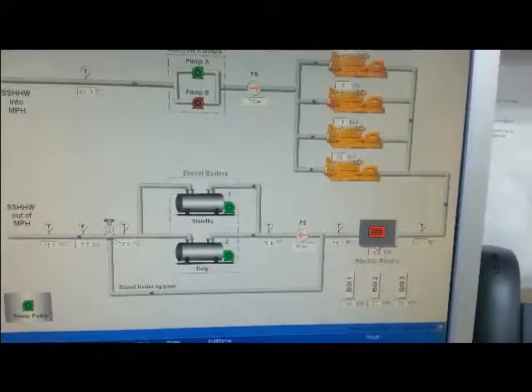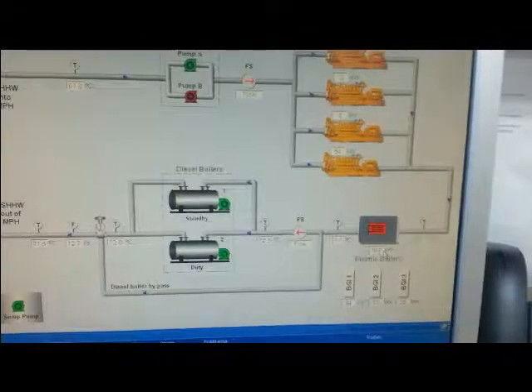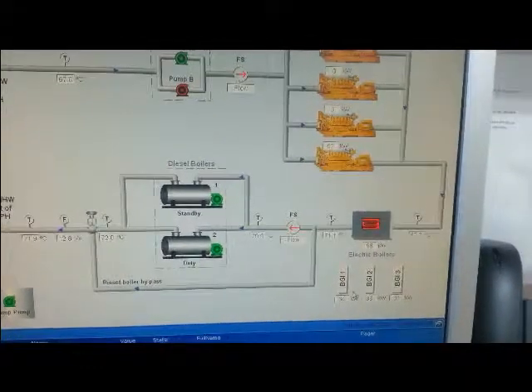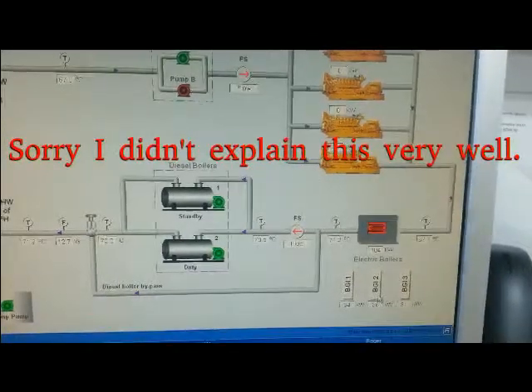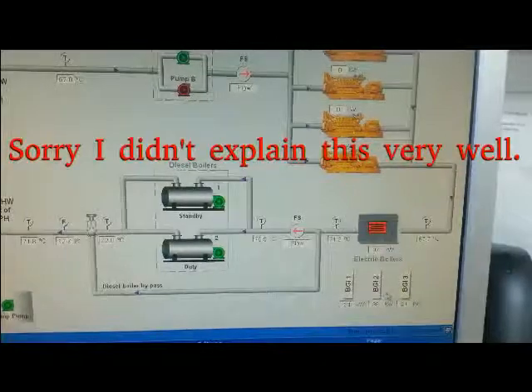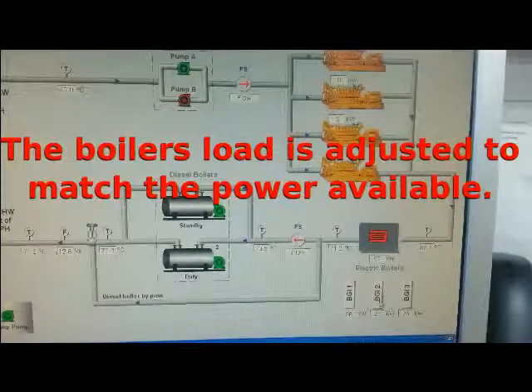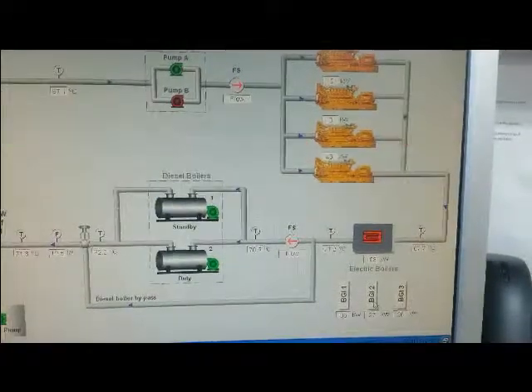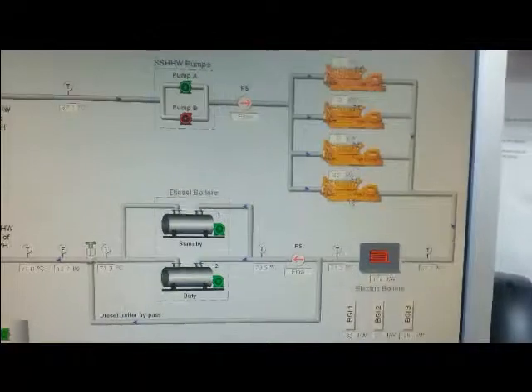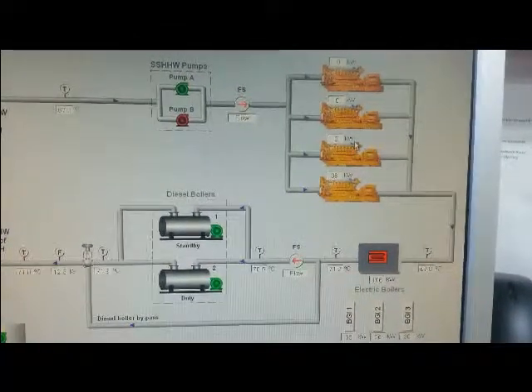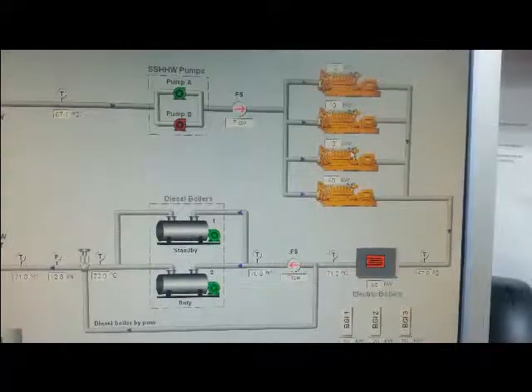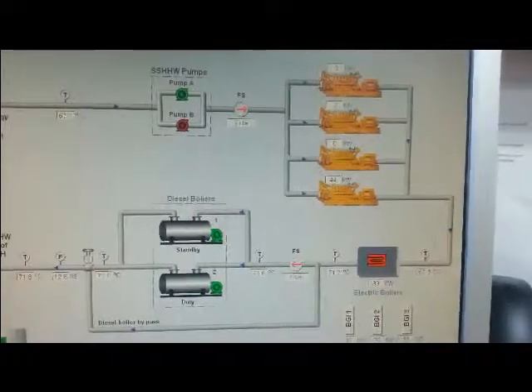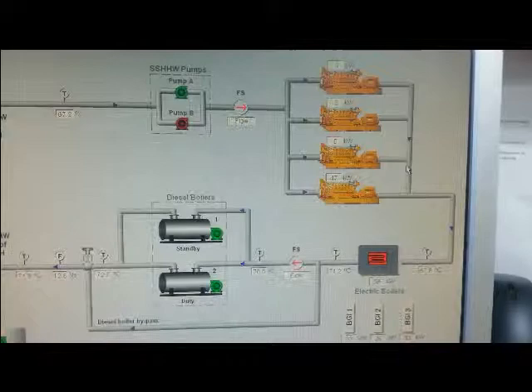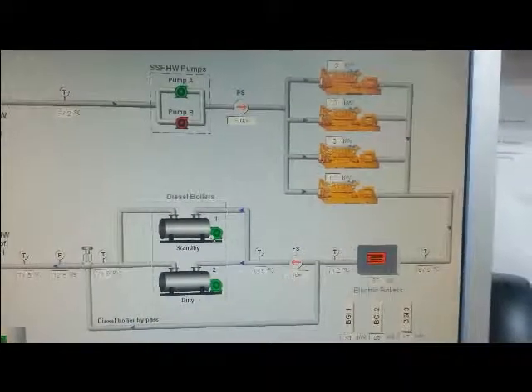We run down here - this is an electric boiler. What it's got is these BGIs, which modulate the load basically, and they make up the difference between the turbines and the actual demand. So basically they are there to regulate the load and give us this heat. If we were running purely engines, we'd have probably two engines running normally, good for 128 kilowatts each. There'd be enough secondary heat coming off those heat exchangers in summer anyway that their boilers don't run.